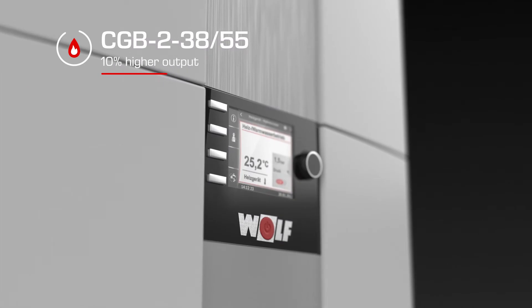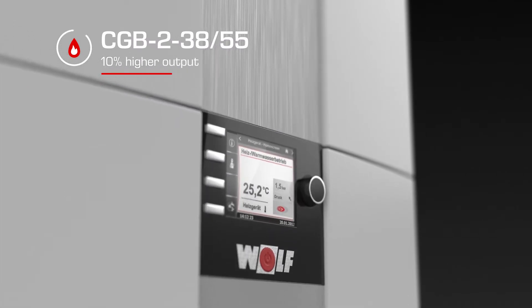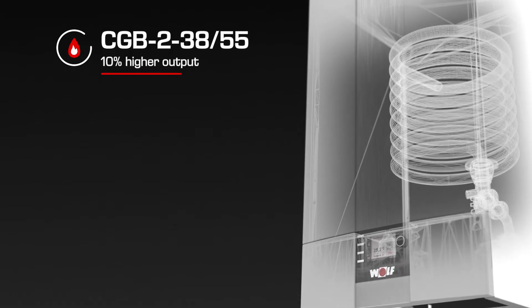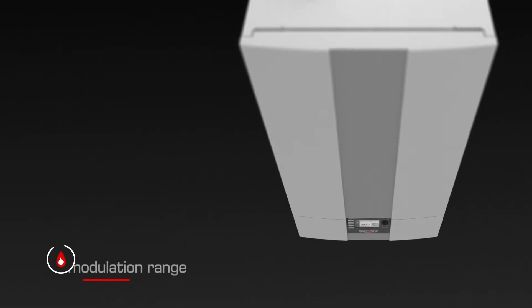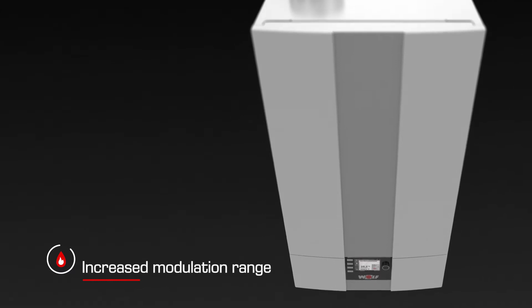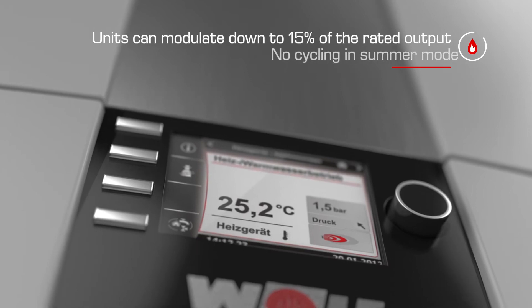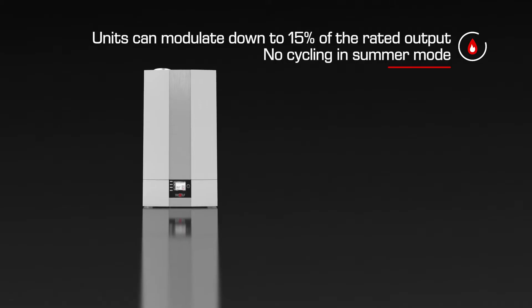Let's have a closer look at the CGB-2-38/55. It has 10% more power than the former model. This power reserve can be an advantage in the apartment building sector. We also significantly increased the modulation range. The units can now go down to 15% of their rated output, which prevents cycling, particularly in summer mode.